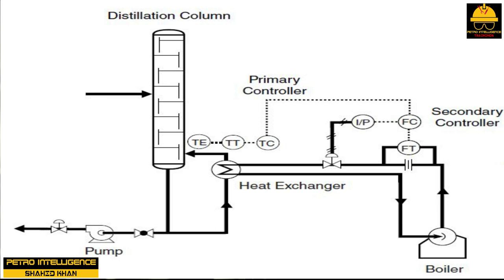In a temperature control loop, a temperature measurement is taken at the furnace or from the exiting charge in large fired heaters. The primary sensors used to detect temperature are thermocouples or RTDs, often called temperature elements. Temperature elements are linked to transmitters that produce a signal sent to a controller, recorder, or indicator. A 4 to 20 milliamp signal is sent to a controller that compares it with a set point — the desired value of a process variable.